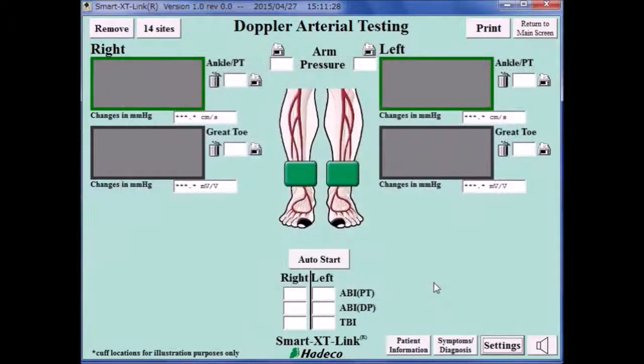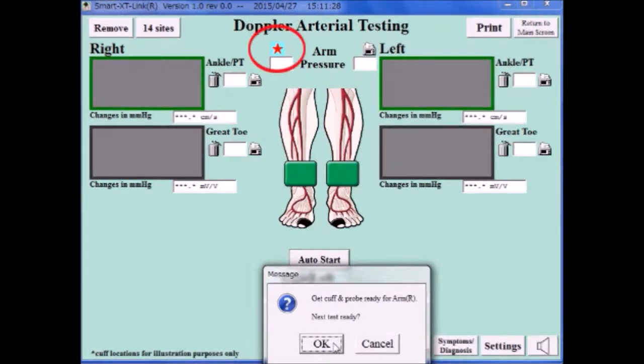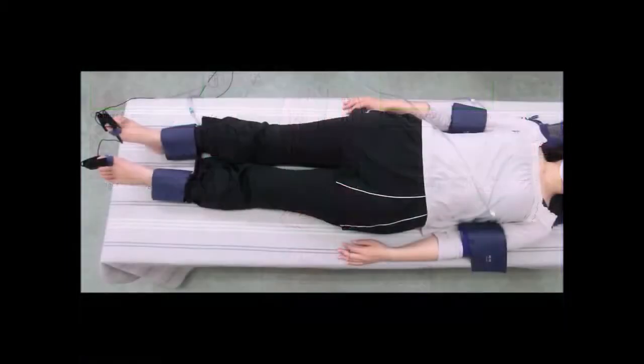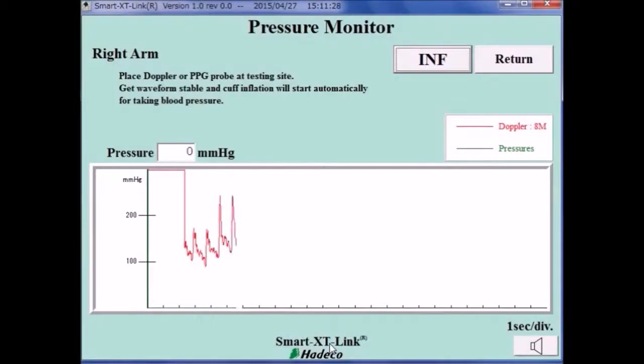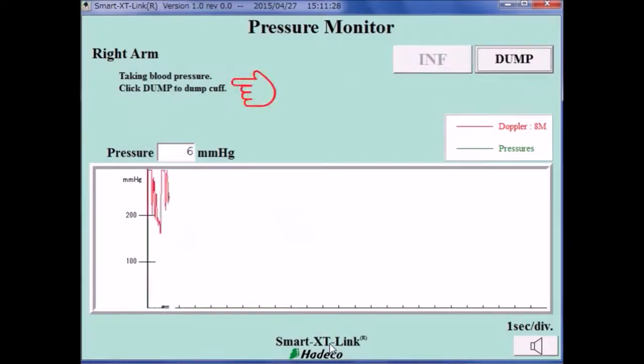Now, Doppler is selected. Select Auto Testing and choose the sequence from the 4 options. Now the first one is selected. Click Save. Click Auto Start and a dialog box will appear. At the beginning of each test, a red star will appear to let you know which site should be tested. Make sure that the cuffs and probes are ready and click OK. Now it is taking the right arm pressure. Follow the guidance on the upper left of the monitoring screen to take the arm pressure.